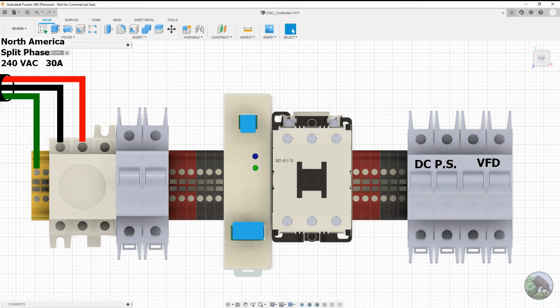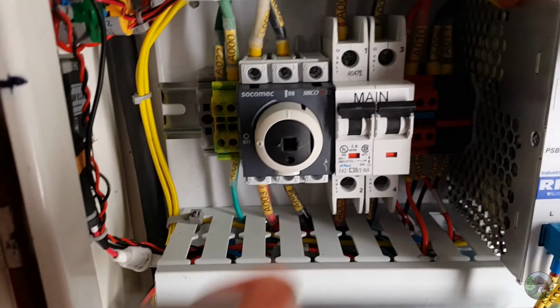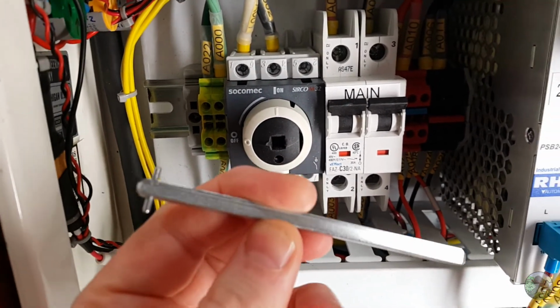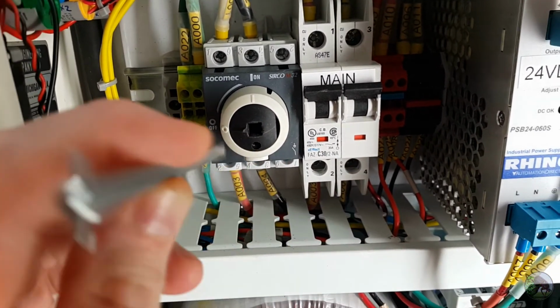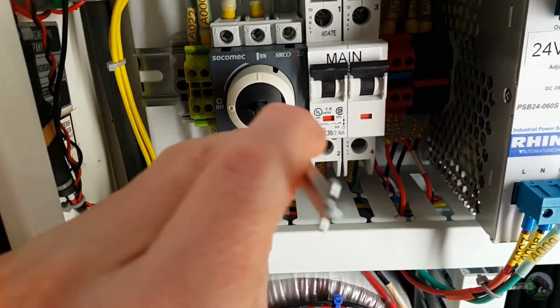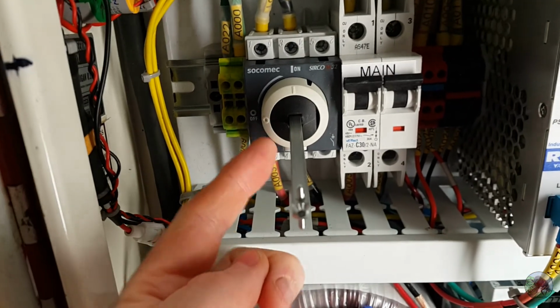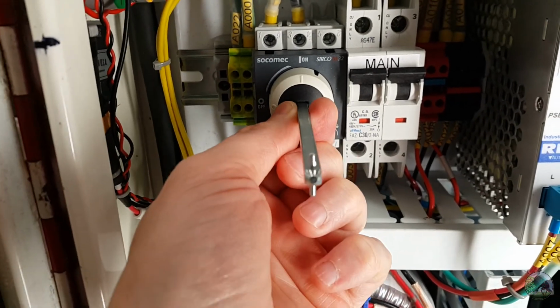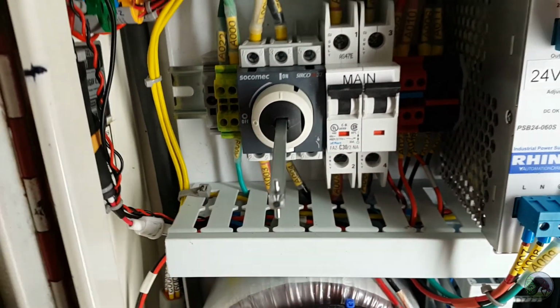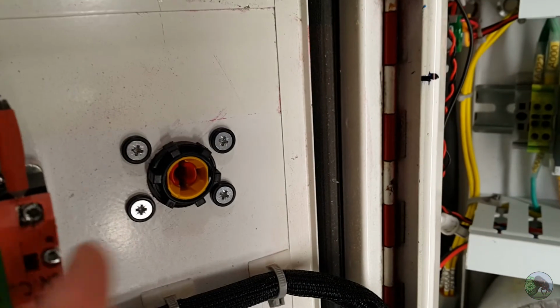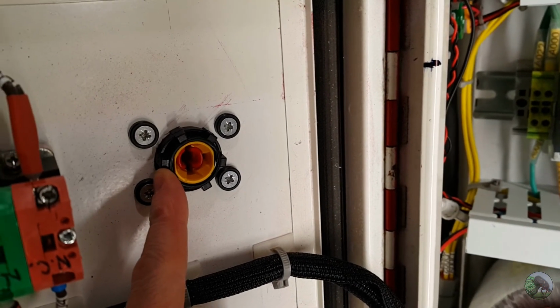Nothing else downstream gets powered at all. So the rotary disconnects come with this rod, which can be cut to any length you need. And then that rod is inserted. And there's actually a little nut which allows you to secure this rod inside there so it won't come out. And then on the door where the actual switch is, it just mates with it.